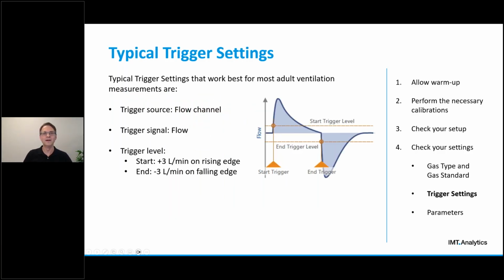Okay, so this means that the flow signal in the flow channel, with a start trigger level at a low positive number on a rising edge and a low negative number on a falling edge of the signal for the stop trigger, typically works perfectly fine. And this is why these, which you can see on the slides, or very similar trigger settings are typically the default trigger settings of your gas flow analyzer. That explains why most of you maybe haven't ever had to touch the trigger settings.